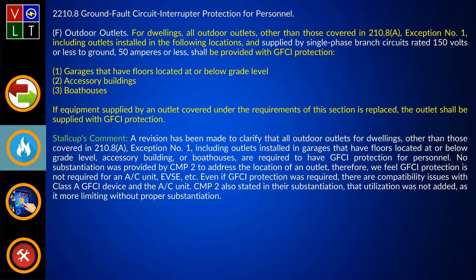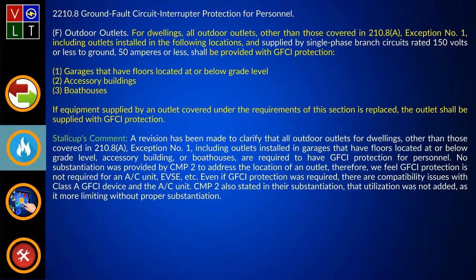It does. As a matter of fact, in our substantiation, we specifically pointed out that there was no substantiation provided by Code Making Panel 2 to address the location of an outlet. Therefore, we felt that GFCI protection was not required for the AC unit, electrical vehicle service equipment, etc. Now, one thing I want to point out, if you go look at the substantiation in the first revision and second revision to 210.8D, Code Making Panel 2 was very specific about cord and plug connected and hardwired, and they didn't care if it was vintage or not, that you needed GFCI protection. But when you got to the substantiation for 210.8F, they magically didn't make any reference to any of that. And I thought that was a telling sign, in my opinion.